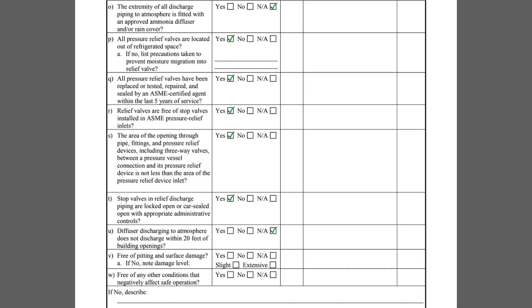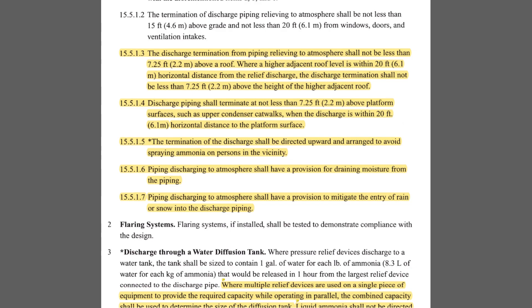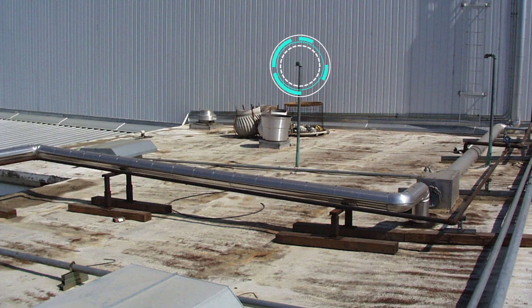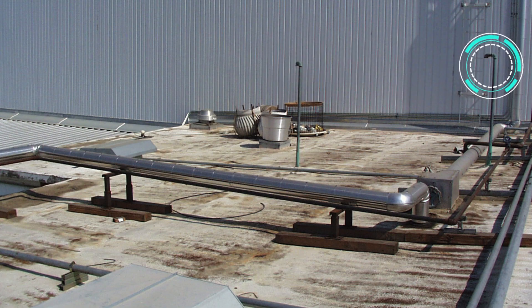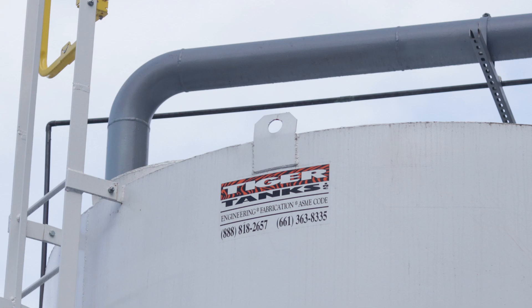Item U is used to assess the relief valve discharge termination location. IIAR Standard 2 states that discharge termination from piping relieving to atmosphere shall not be less than 7.25 feet above a roof or within 20 feet horizontal distance of an adjacent building roofline. These relief valves are not terminated at an adequate height. When the relief valves terminate into an ammonia diffusion tank, the question should be marked N/A.